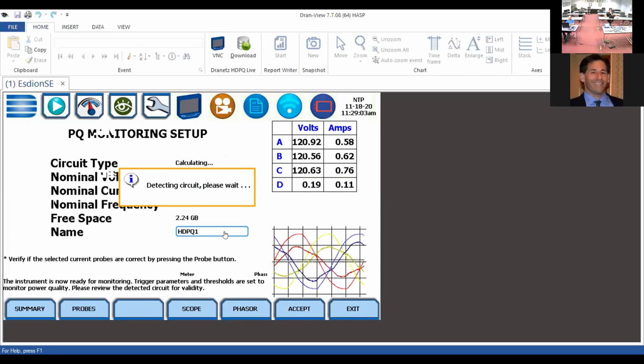What the instrument does now is it's assuming that you've already made your voltage and current connections to a given circuit. The instrument is then going to sense the number of channels that you're using as far as voltage. It's going to sense what those values are, and then it's going to come back and say, this is my best guess as far as the circuit type that we're connected to. And you can see in this scenario here, we're connected to a Y circuit with a nominal voltage of 120 volts.